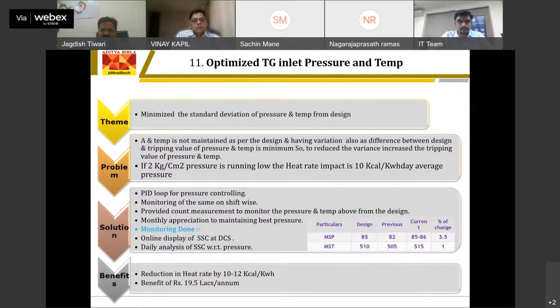Now, sir, we have done one more process optimization. Basically, our turbine is designed for 85 kg per centimeter square pressure, and temperature is 510. Desk operators were maintaining 85, and then the average was coming to 82, 83. What we did, we asked them to maintain between 85 to 87 and temperature 510 to 515. By that, we are able to maintain the 24-hour average pressure and temperature at our design level.